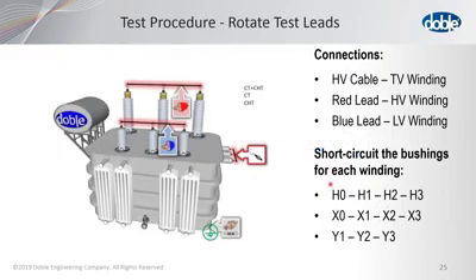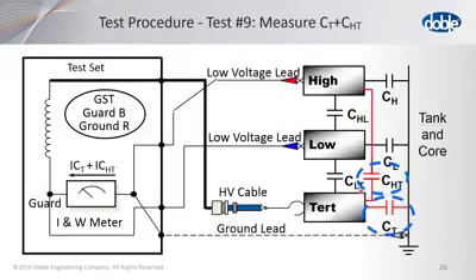Now the third test setup, or the third transformer, is between the high and the tertiary windings. We've rotated the leads again. We take whatever is on this lead, on this connection, and move it here. Then we take the red lead that was here and move it up to here. We take the blue lead and move it over to here. Again, if you forget the procedure, you can look at the connections in DTA. The short-circuiting of the bushings remains the same, of course. Now in this third two-winding transformer, we are energizing the tertiary, and the CHT and the CT are being measured. That's test number 9.